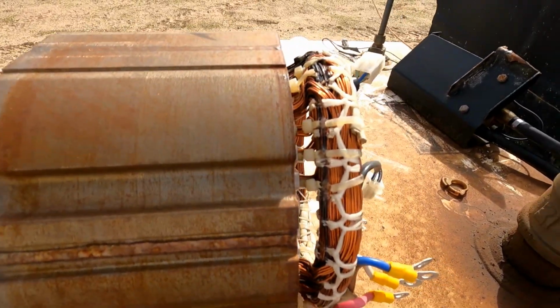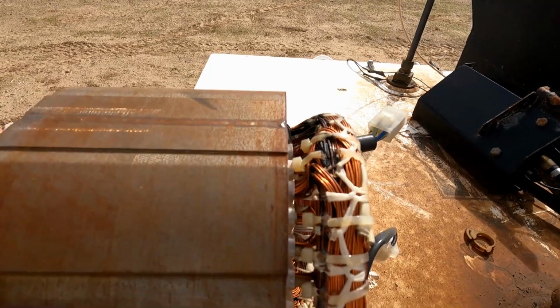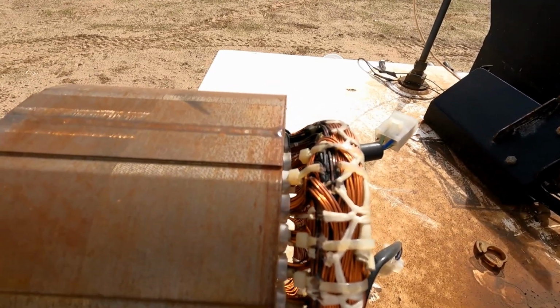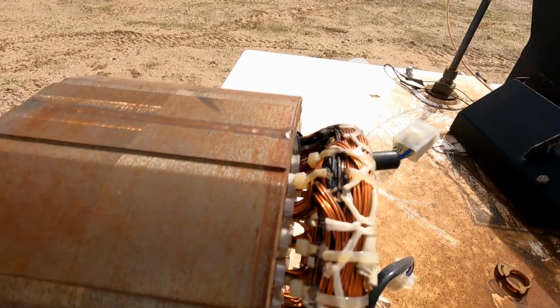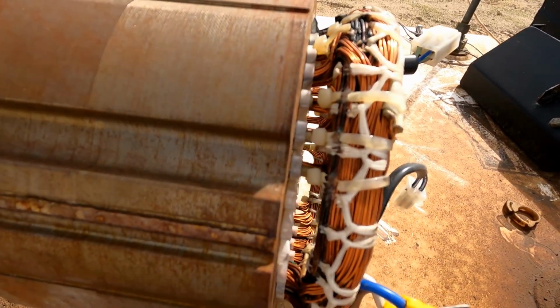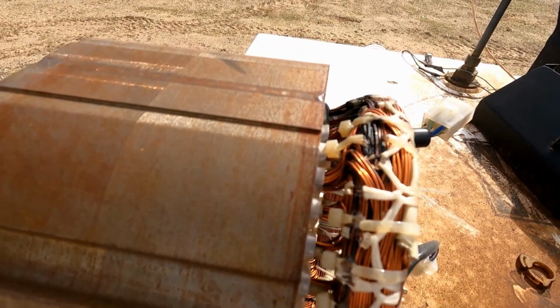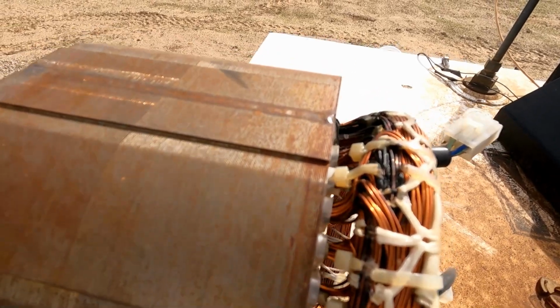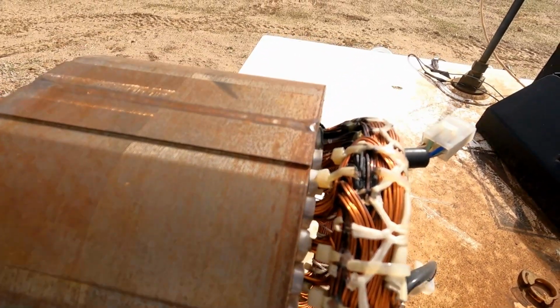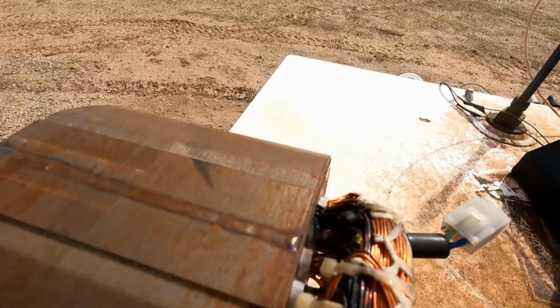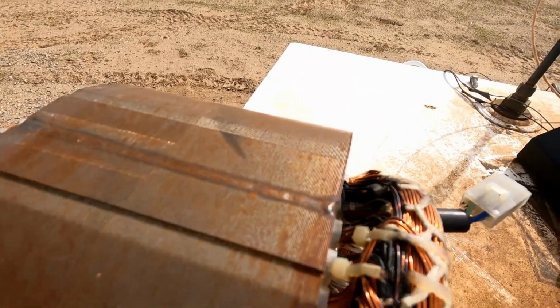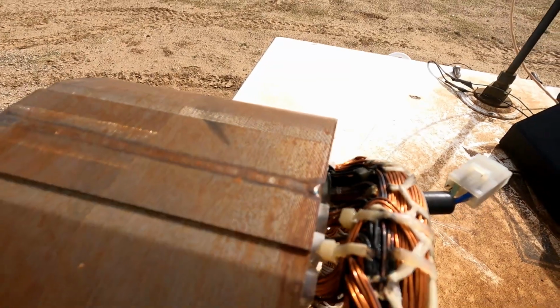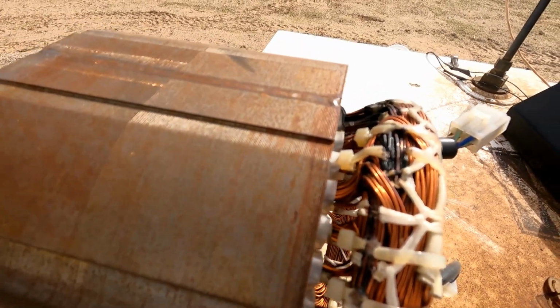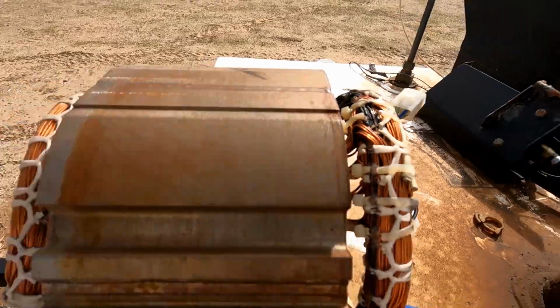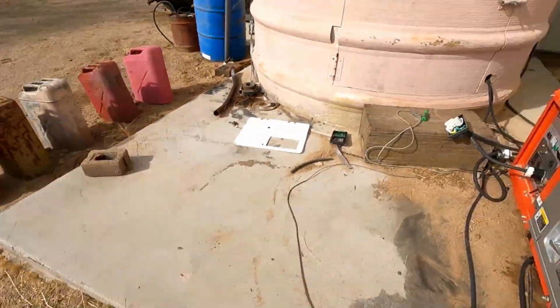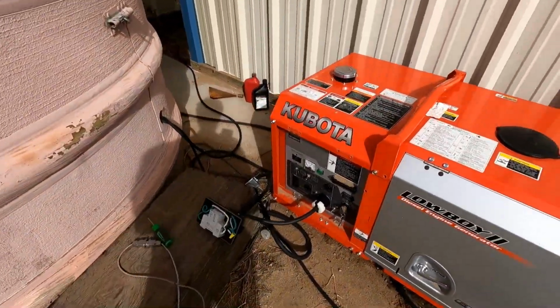Now, the suspicion that we have here is that over time, and in this case it took about 9 years or so, those spikes can slowly wear at and degrade the insulation and ultimately result in a failure or short of the AC output to the stator, causing the generator to fail. So the solution becomes obvious: surge protection.